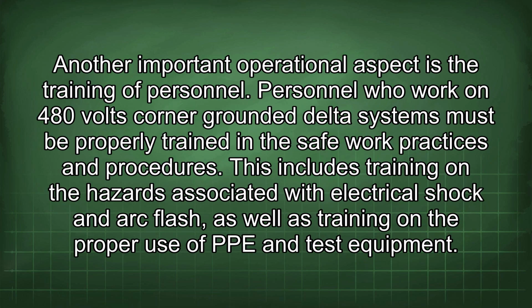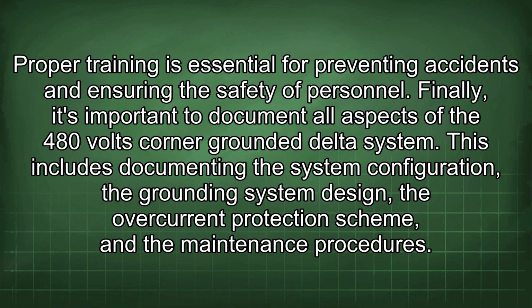Another important operational aspect is the training of personnel. Personnel who work on 480 volts corner-grounded delta systems must be properly trained in the safe work practices and procedures. This includes training on the hazards associated with electrical shock and arc flash, as well as training on the proper use of PPE and test equipment. Proper training is essential for preventing accidents and ensuring the safety of personnel. Finally, it's important to document all aspects of the 480 volts corner-grounded delta system. This includes documenting the system configuration, the grounding system design, the overcurrent protection scheme, and the maintenance procedures.